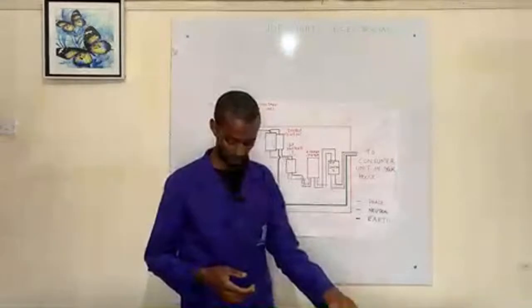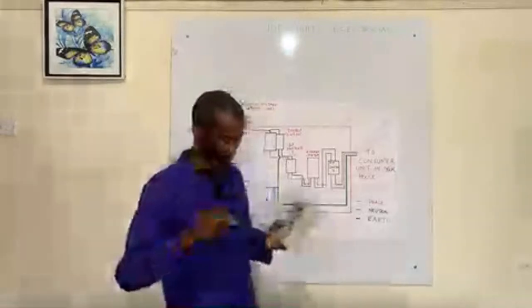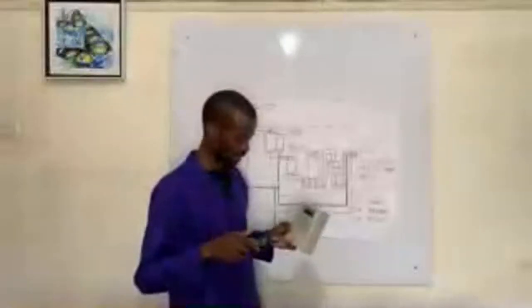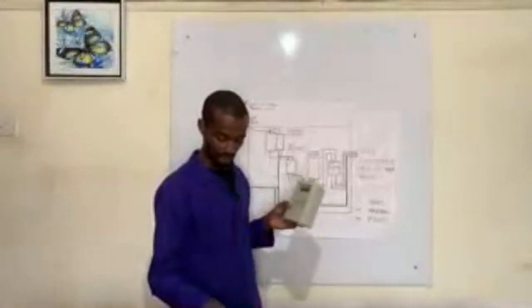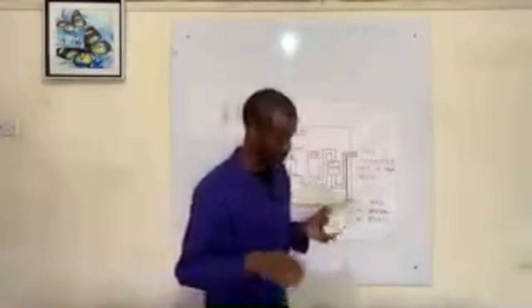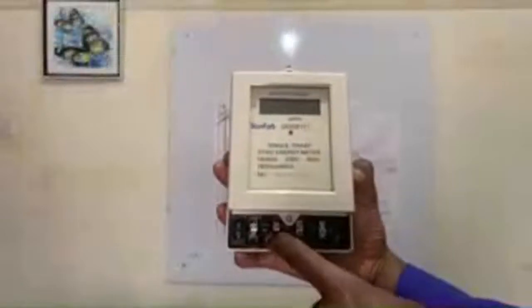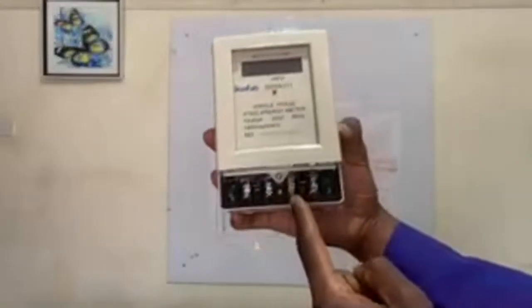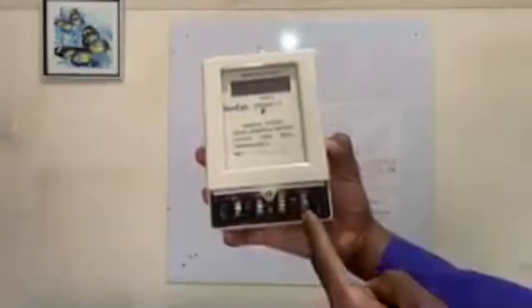So when we get to the energy meter, it has several connections. Most energy meters have four, with incoming and outgoing terminations. For the sake of this energy meter here, what you can see is an incoming phase and an outgoing phase, connected here at these first terminations. We also have an incoming neutral connection and an outgoing neutral connection that will be connected.